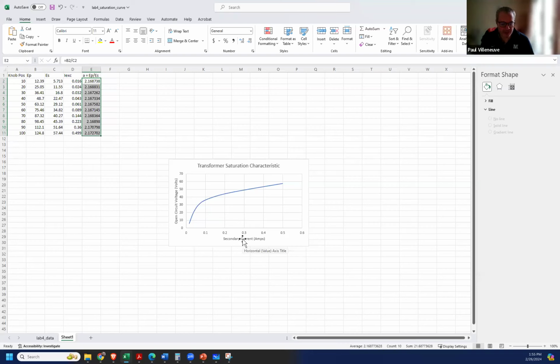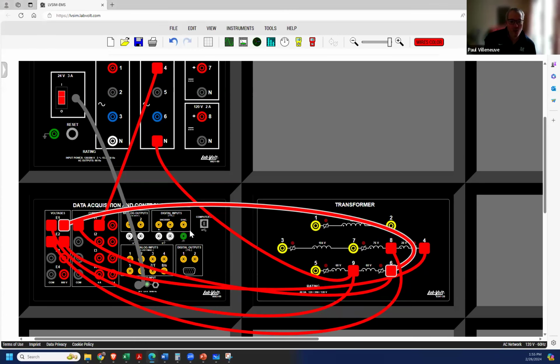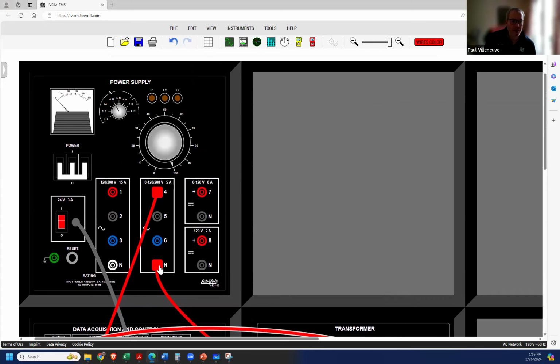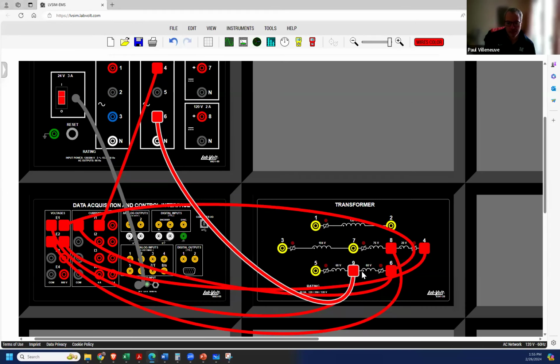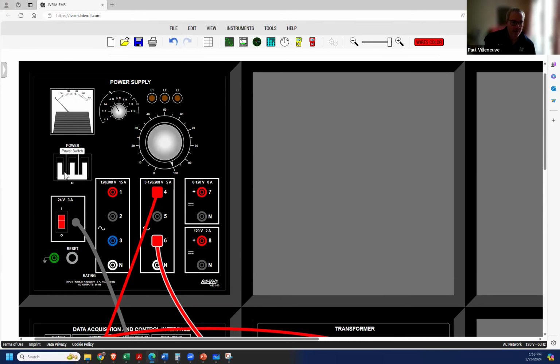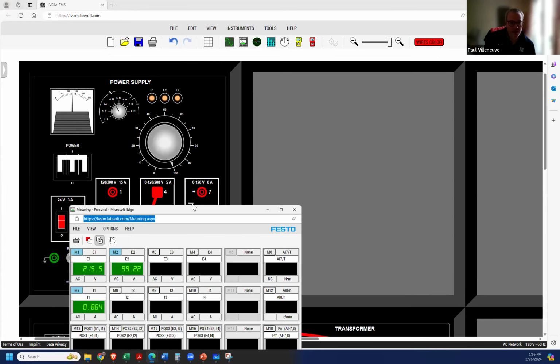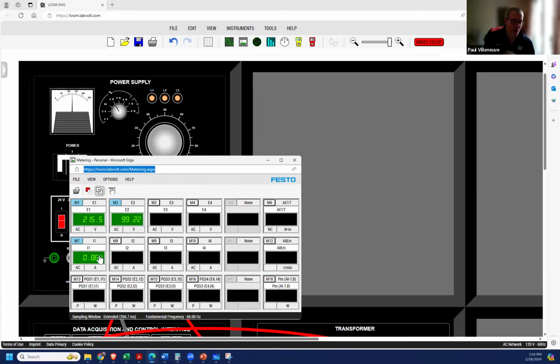There's a reason we can do that, but at some point we won't be able to get there from here. If I drove it over here, which is basically pushing a 60-volt winding at 208 volts, it might not work for us. Looking at the data, I've got 0.9 amps occurring, and I still have approximately that 2-to-1 ratio.